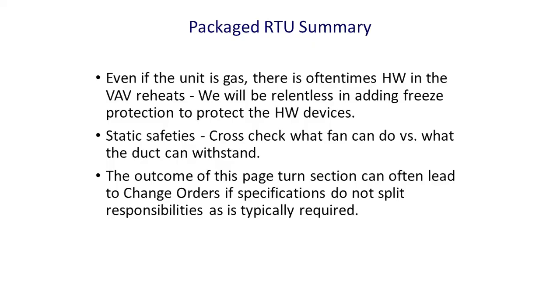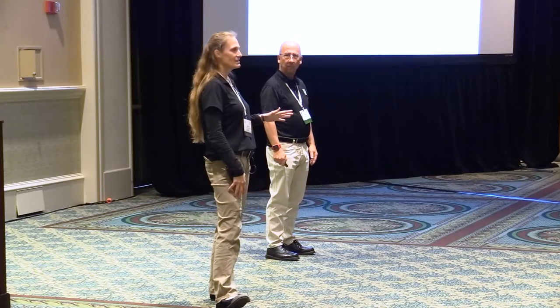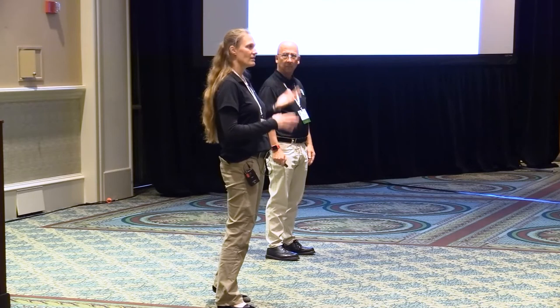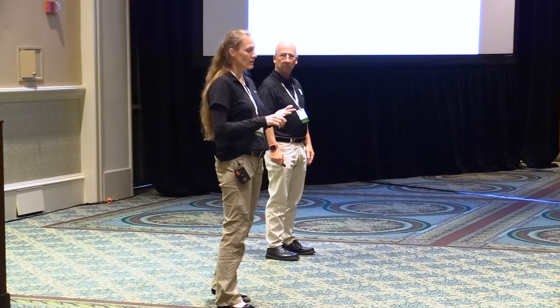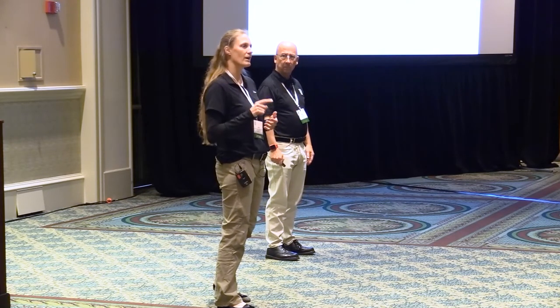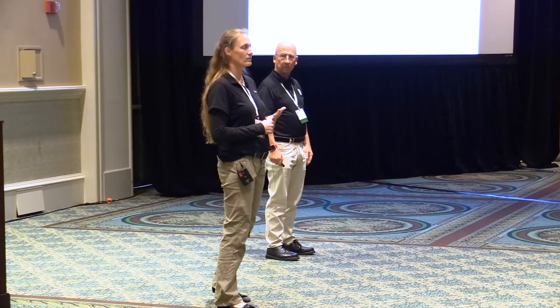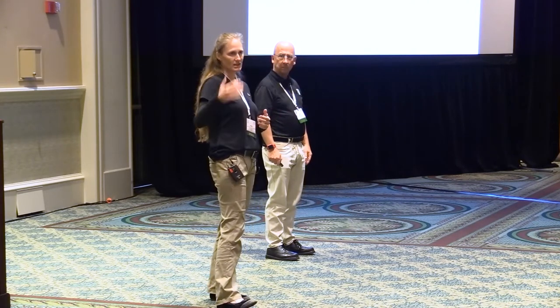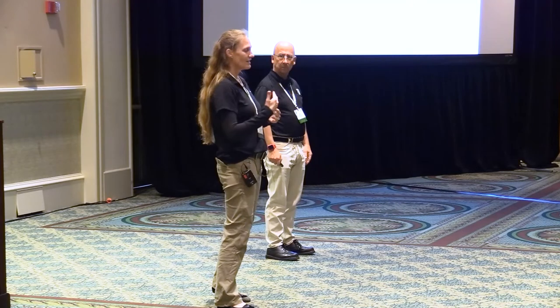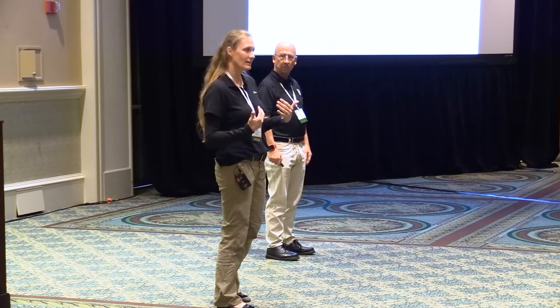So even if the unit is gas, there's many times, you know, why do you need a freezestat if it's gas and DX? I mean, what are we protecting? Well, we're protecting all the hot water devices that are downstream of the unit. And we've had a number of instances where we've had a unit with gas and DX, and we have pushed to have hardwired freezestats or hardwired low limits installed in the ductwork after the unit. And there is a lot of pushback to us.